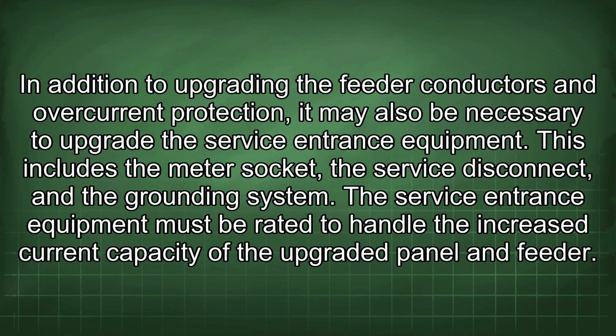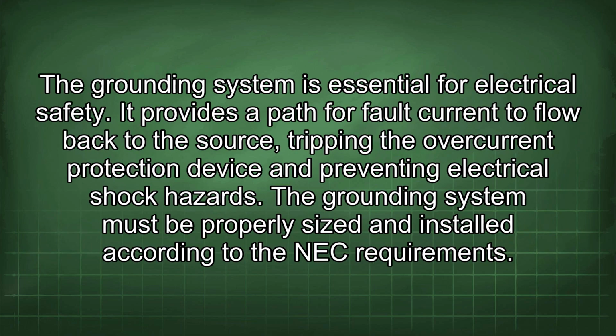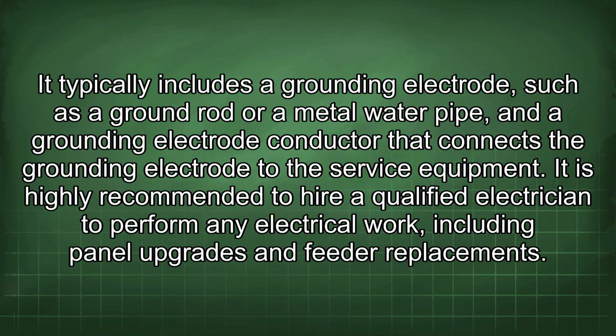In addition to upgrading the feeder conductors and overcurrent protection, it may also be necessary to upgrade the service entrance equipment. This includes the meter socket, the service disconnect, and the grounding system. The service entrance equipment must be rated to handle the increased current capacity of the upgraded panel and feeder. The grounding system is essential for electrical safety. It provides a path for fault current to flow back to the source, tripping the overcurrent protection device and preventing electrical shock hazards. The grounding system must be properly sized and installed according to the NEC requirements. It typically includes a grounding electrode, such as a ground rod or a metal water pipe, and a grounding electrode conductor that connects the grounding electrode to the service equipment.